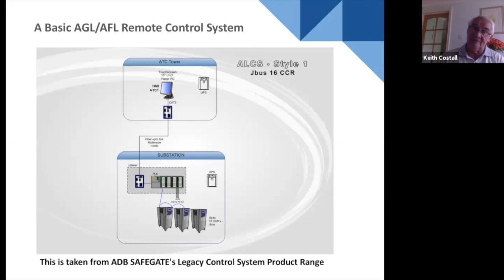Hardwire is quite good for maintenance because you can say, oh, it's either 24 volts or 48 volts—you can go in and check you've got a voltage. But with data communication, you can't see it that way. So the question is, do you understand this technology? It's electronic and IT technology involved here, not just changing bulbs in the airfield.